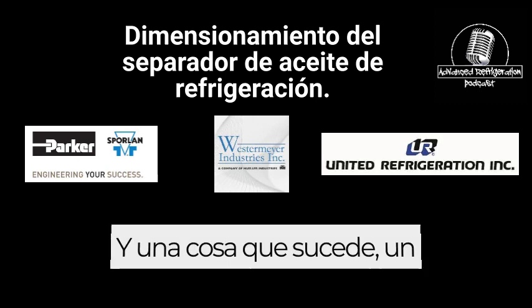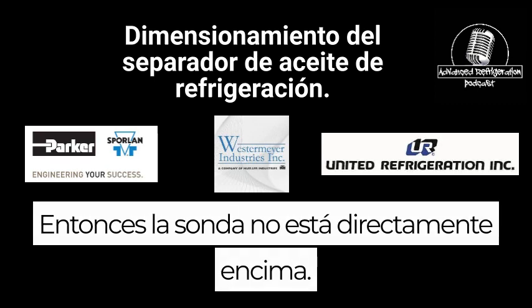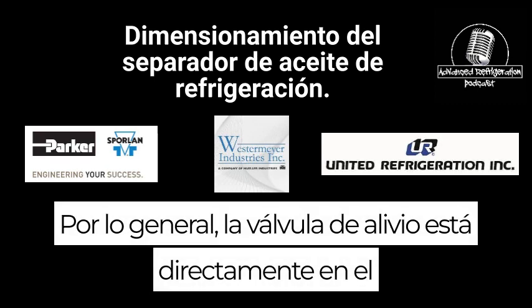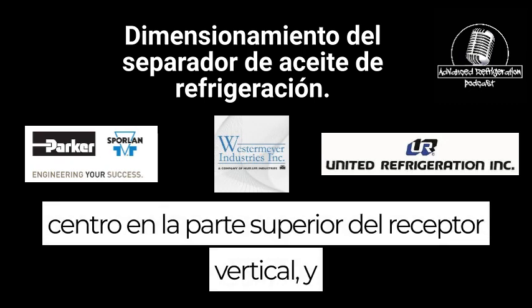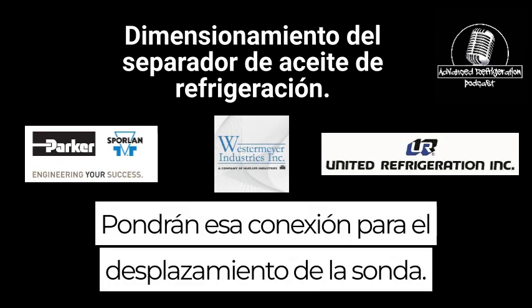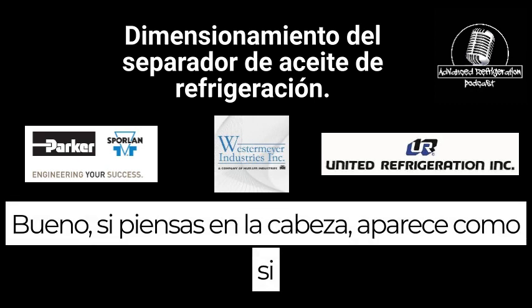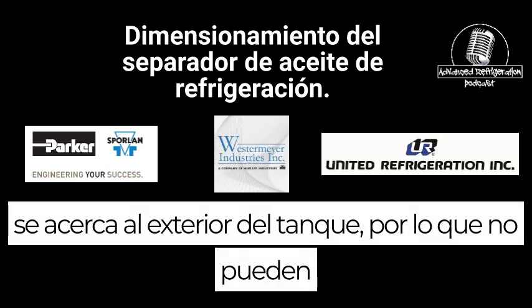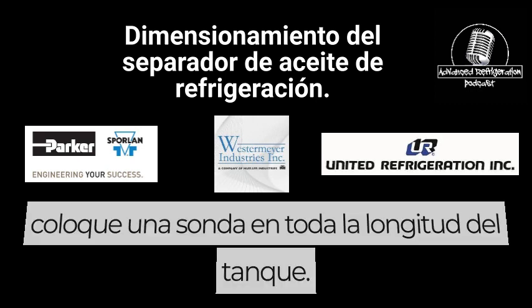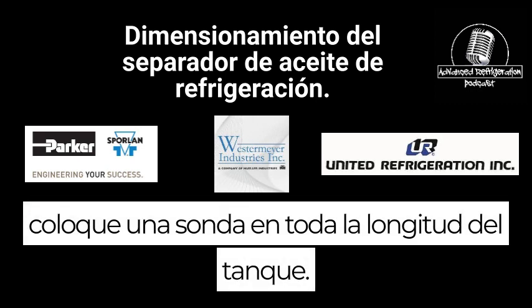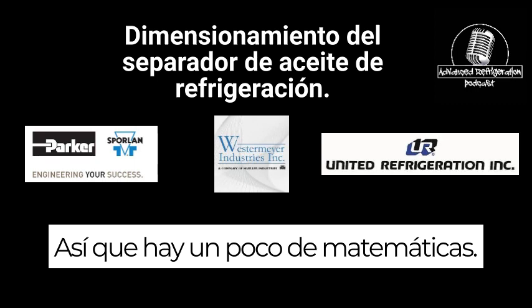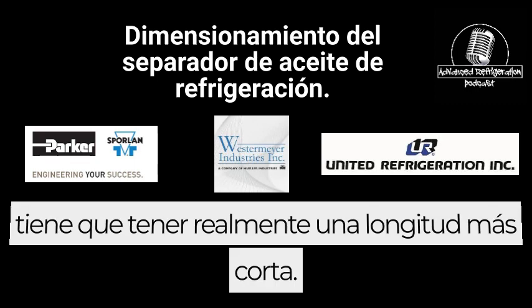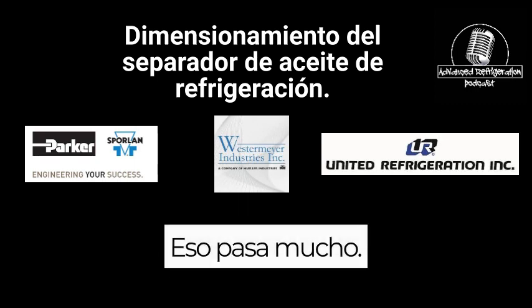Right. And a lot of manufacturers do this: the probe's not directly on top. Usually the relief valve is directly in the center on top of the vertical receiver, and they'll put the connection for the probe offset. If you think about it, the head comes up as it gets closer to the outside of the tank, so they can't put a probe at the full length of the tank. So there is a little bit of math that comes into it, where you have to have a shorter length. That happens a lot.